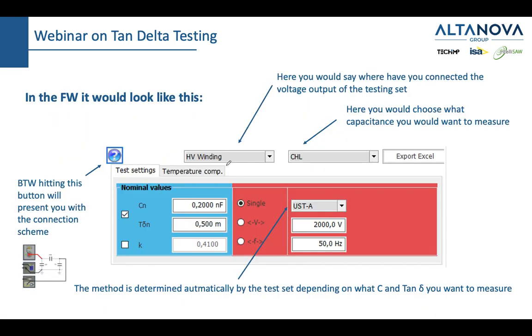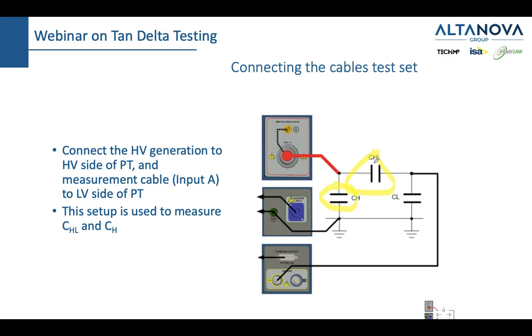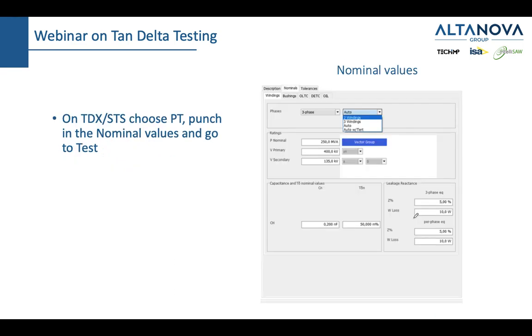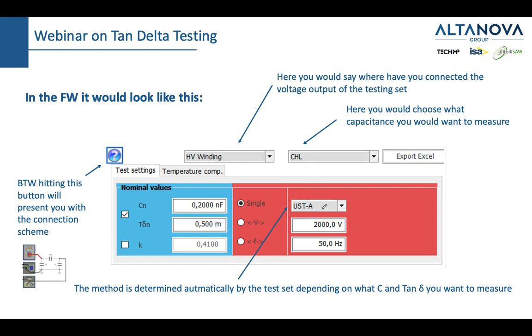And then, if you're not sure how to connect, of course, you just press the question mark button and you will get this nice scheme. And also, as you have chosen this and this, automatically the system chose what method will be used. Will it be a UST or a GST method? This is a topic for our next discussion. UST means ungrounded specimen test, and GST means grounded specimen test. Just as a preview, if you want to measure CHL, you will use a UST, because this part of insulation is not grounded on any side, while this specimen is grounded, and this specimen is grounded on one side. So you can see that when I choose CHL, a UST method is chosen.